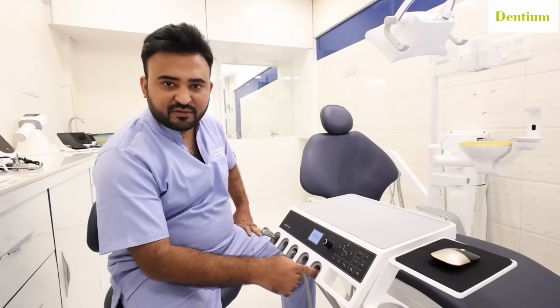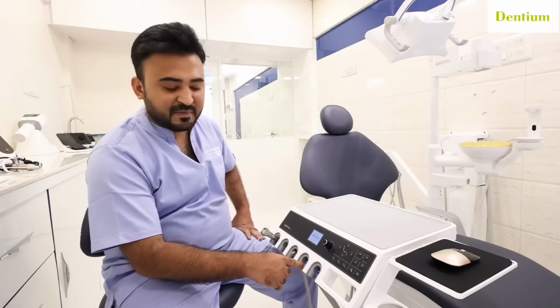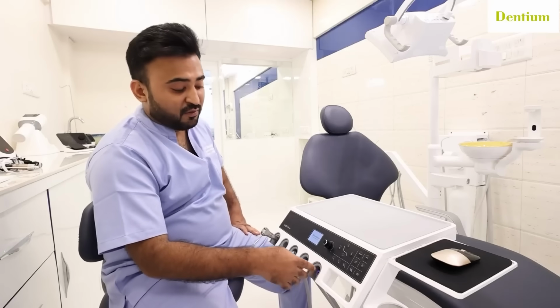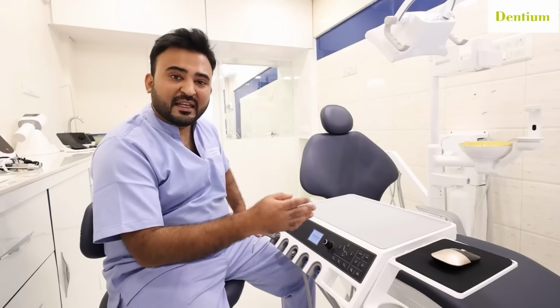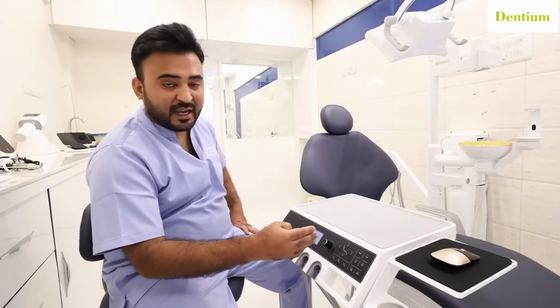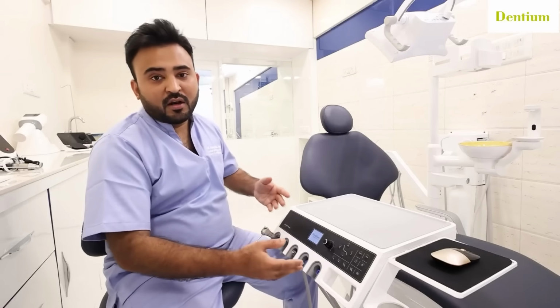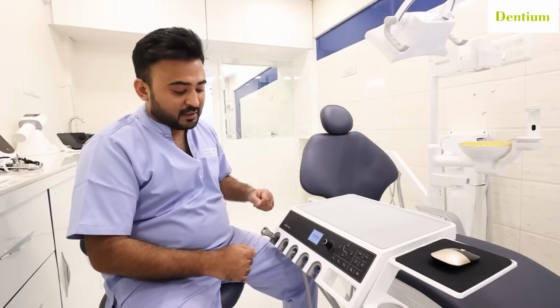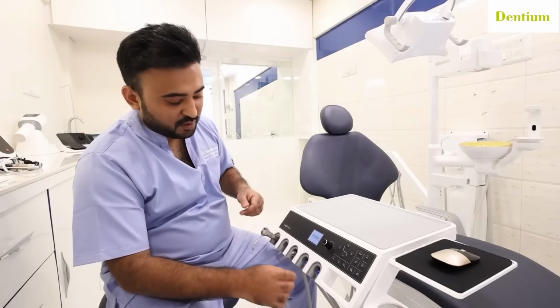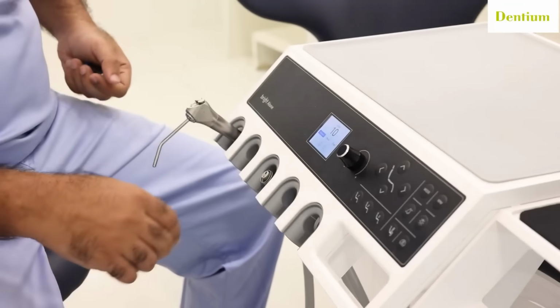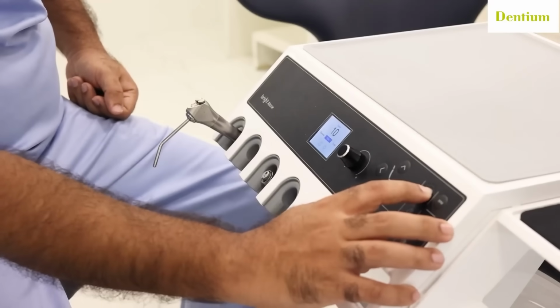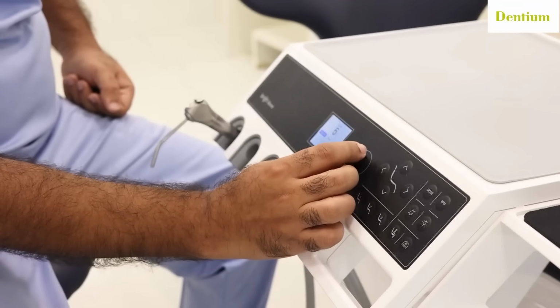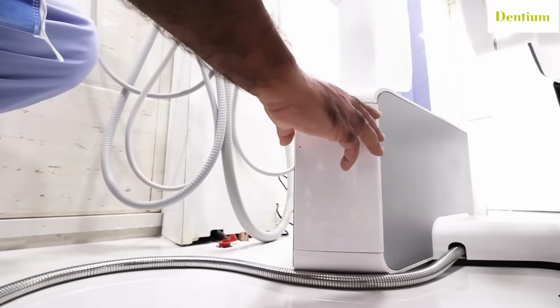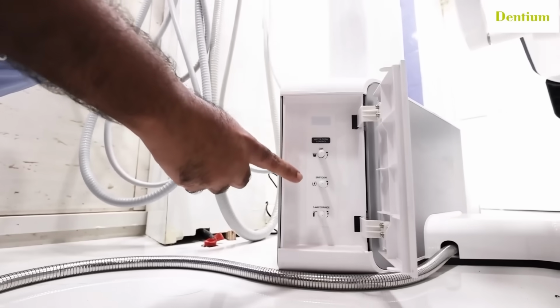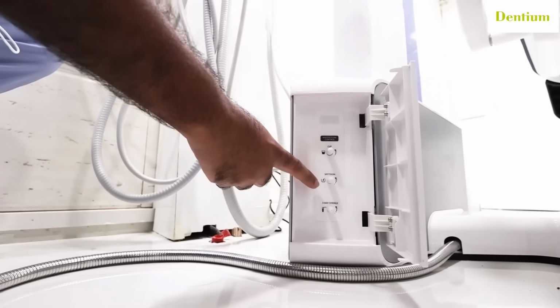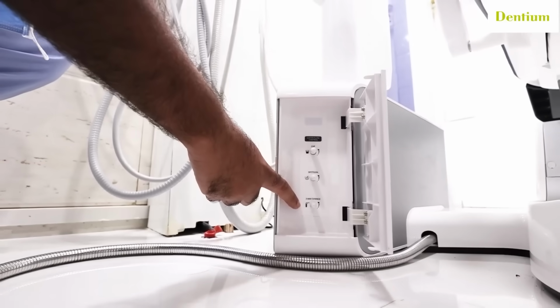So let's go with the 4th and the 5th option. The 4th is for your low speed handpiece and the 5th is for your scaler. If you want to use this attachment, you need to have an inbuilt original NSK micromotor and original NSK scaler, or you can have your external scaler and external micromotor. Let's imagine we have an original NSK scaler over here. As soon as you lift it, the display screen will show general, perio and endo mode, and you can select whatever you want to. You can select whatever speed you want to. This is a great feature. You can also adjust the speed of water of your 3-way syringe, your spittoon and patient's plastic cup.